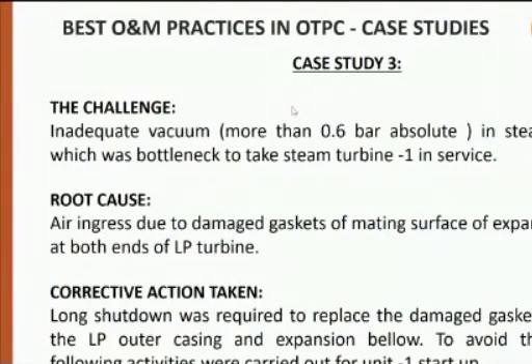So we went to the field and observed where the leakage was coming from. We observed that the parting plane, where the new gasket was installed during the shutdown, had some problem, and there was air ingress through that parting plane. So now it was a very big problem for us. If we had to go for unit operation, we would have to take a shutdown, and that would cost us almost 10 to 15 days. That too in the time of Corona. You can understand that during the Corona pandemic, it is very difficult to ask experts to visit the plant and do this type of outage. So we thought we should find some other method to seal this leakage portion.